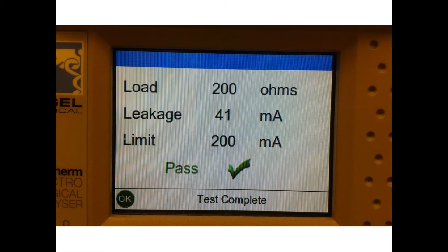For the LigaSure, the system must be in debug mode. You press it and get into debug mode with the code again, 423213. Then you go through the steps and connect, making sure you have the 200 ohm. It's basically set up on the Rigel unit already, but that is what you're looking for, the 200 ohm. Then you go through the procedures and check to make sure it does not exceed 130 milliamps. And this is a case where the manufacturers are doing better than the minimum standard.